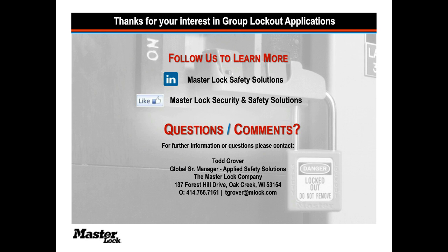any job lock holder wanting to go hands-on or go work on the equipment would have to apply a personal lock to protect themselves. I would say that I have not heard of multiple job lock keys being present on the same shift, because the job lock is usually unique to the lockbox, but it is typically one job lock key per work shift in the hands of the responsible party controlling the overall lockout activity.